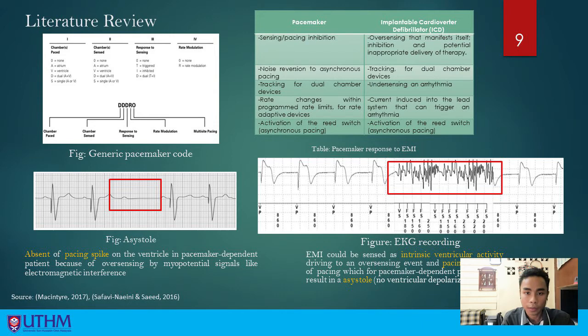For example here, due to the EMI, the oversensing of myopotential signals leads to the absence of pacing spike on the ventricle. This condition is called asystole in pacemaker-dependent patients, which is a condition where there is an absence of ventricular contraction. The other example also shows the EKG recording, where the EMI could be sensed as intrinsic ventricular activity, leading to an oversensing event and pacing inhibition.